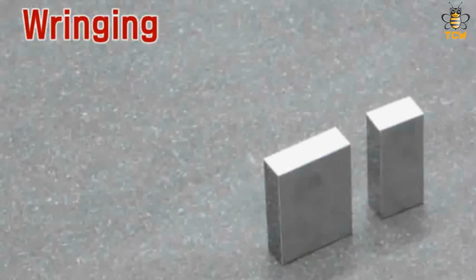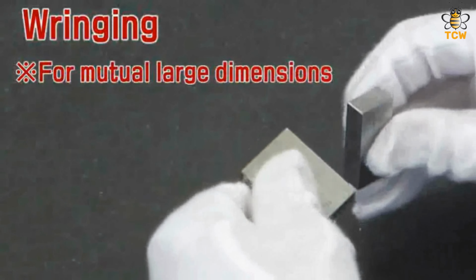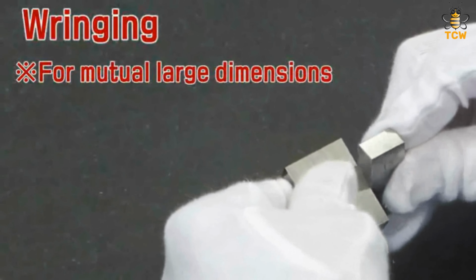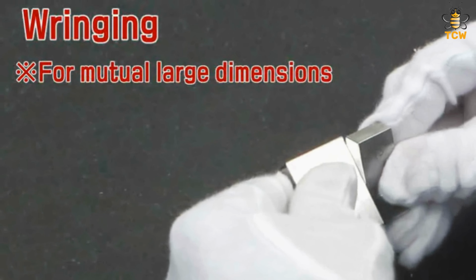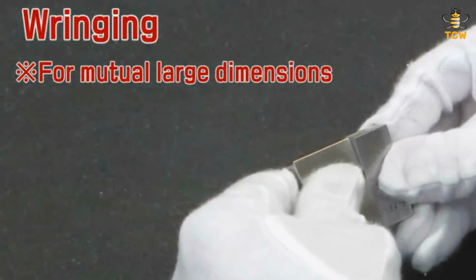Method for stacking gauge blocks, or ringing. Prepare 2 gauge blocks to be stacked. To stack 2 thick gauge blocks, stick the 2 sides of the gauge blocks crossed. Then gently rotate until both faces are well attached.